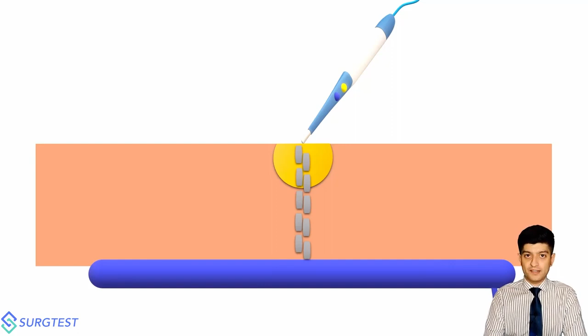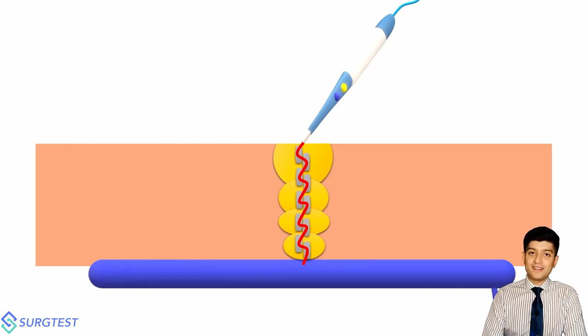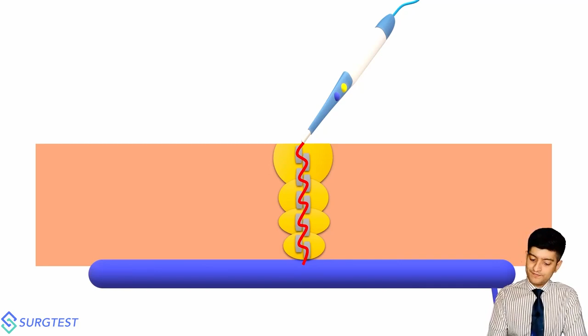So this metal is going to continue conducting electricity, and this current is going to zigzag all the way across down to the dispersive electrode. Now, because the electric current is moving along the path of least resistance, and because this metal is never going to stop conducting electricity, all of the tissue that is present around this area now gets denatured, and you'll end up having much more energy delivery within the tissues at a much deeper level than if you did not have this metal intervening.